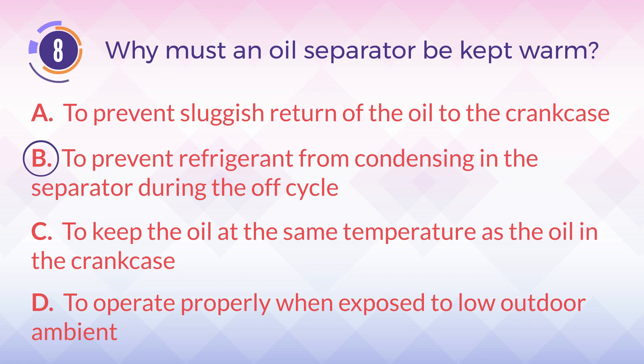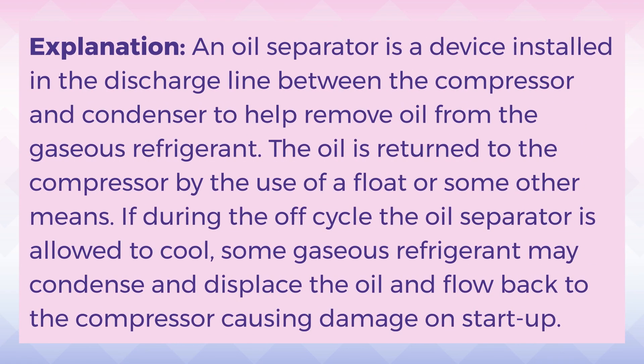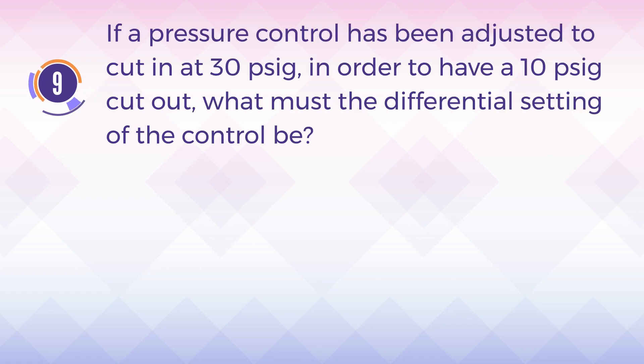The answer is B, to prevent refrigerant from condensing in the separator during the off cycle. An oil separator is a device installed in the discharge line between the compressor and condenser to help remove oil from the gaseous refrigerant. The oil is returned to the compressor via a float or other means. If during the off cycle the oil separator is allowed to cool, some gaseous refrigerant may condense, displace the oil, and flow back to the compressor causing damage on startup.